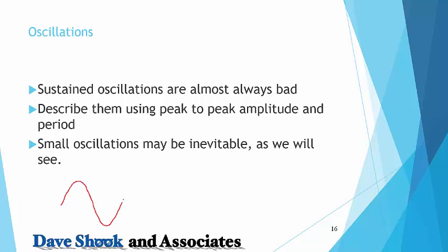And so let's say we have an oscillation in our controlled variable, and it doesn't have to be a sinusoid. Frequently they are not sinusoidal, but they'll have a period, which is peak to peak. Sometimes it may be easiest to count several cycles and pick the total duration, and thus calculate an average period.